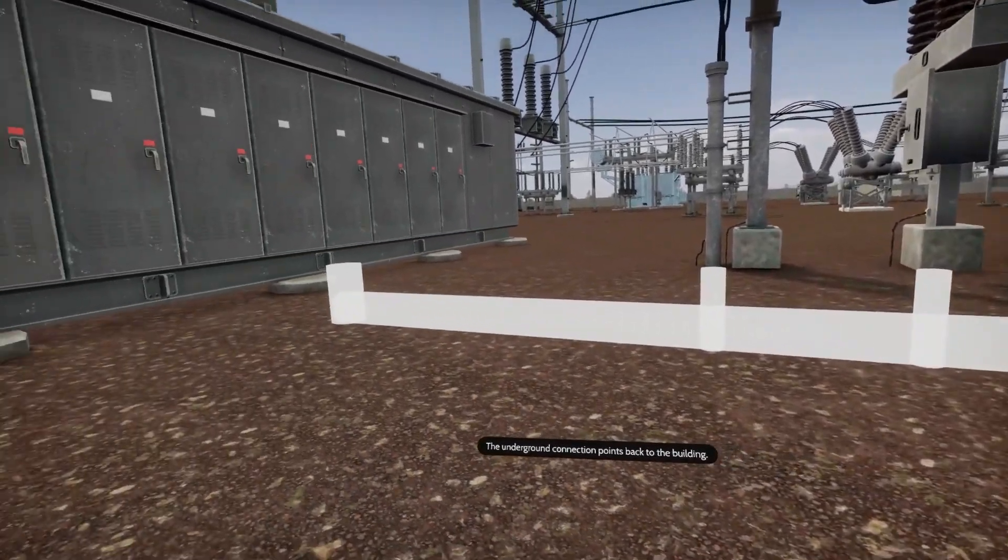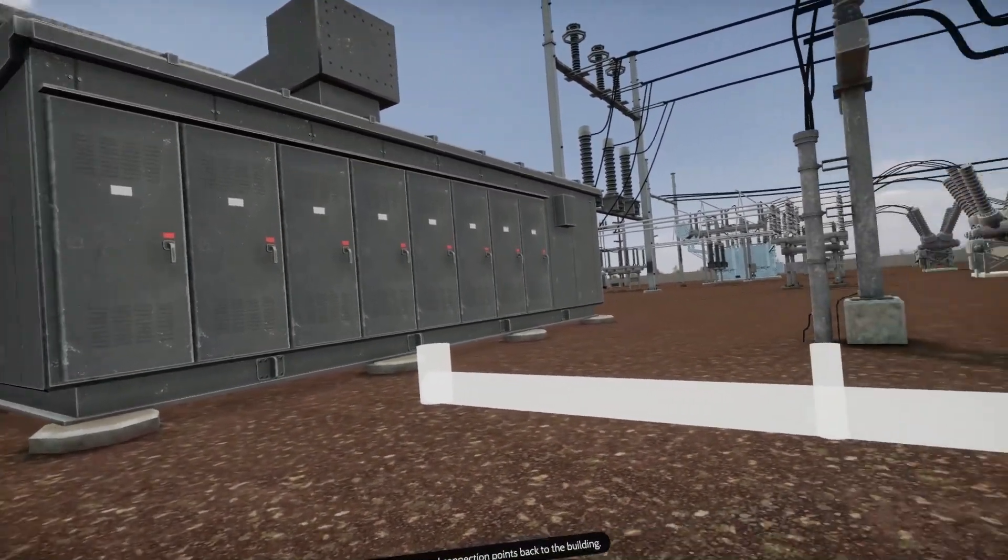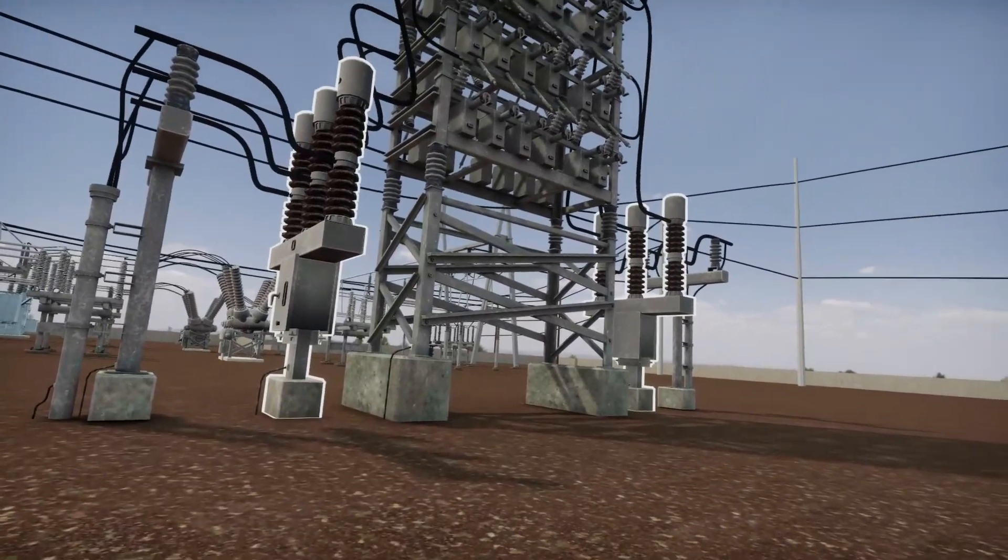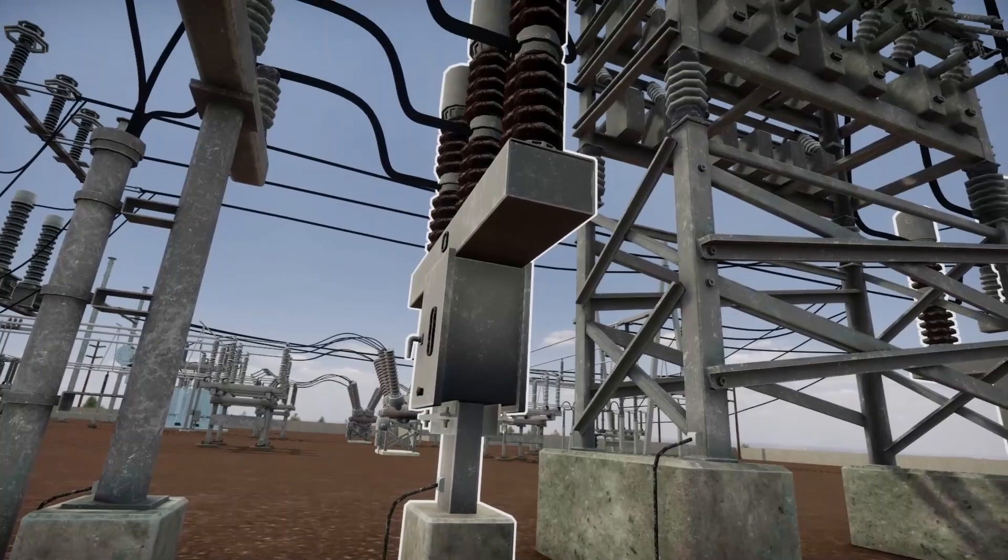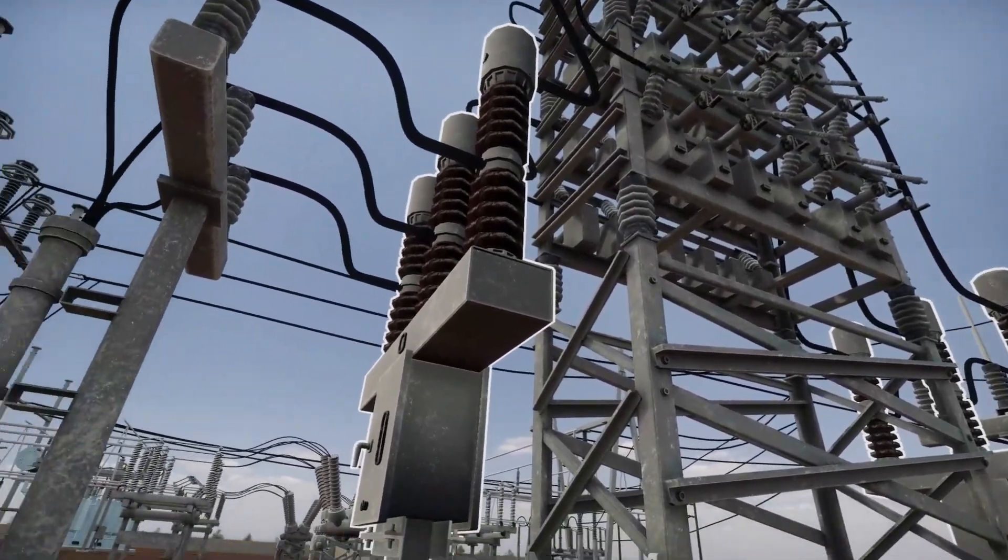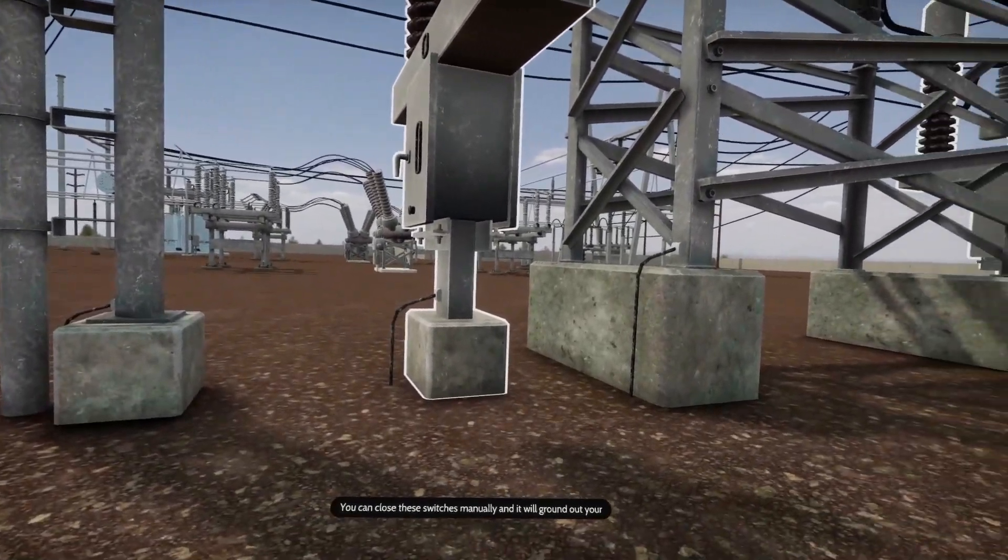The underground connection points back to the building. These switches are if you have to work on this capacitor bank system. You can close these switches manually and it will ground out your capacitor banks and the frame.